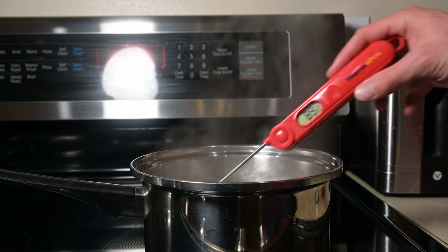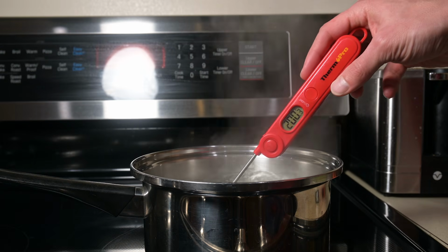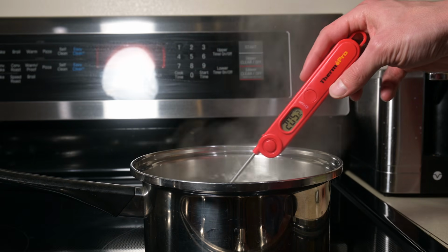So what do you do if the results of the ice water test and the boiling water test don't match up? You can take the differences between the two and average them, and that will give you the best between both of those. However, if your boiling water temperature is way off, you might have messed up that test because the ice bath method is much easier to do correctly and relies on fewer variables. So if you're in a pinch, just go ahead and use the ice bath method and you should get pretty good results.